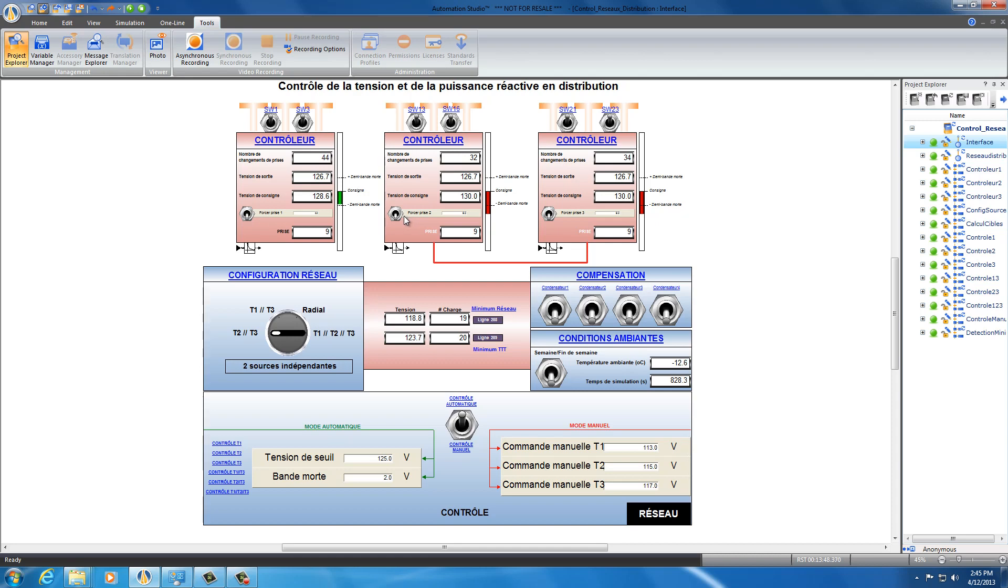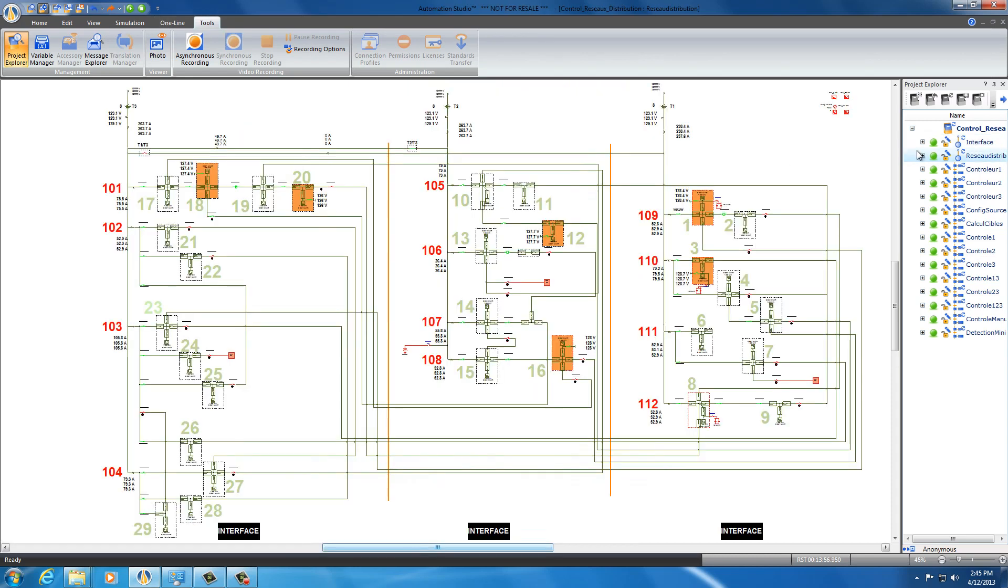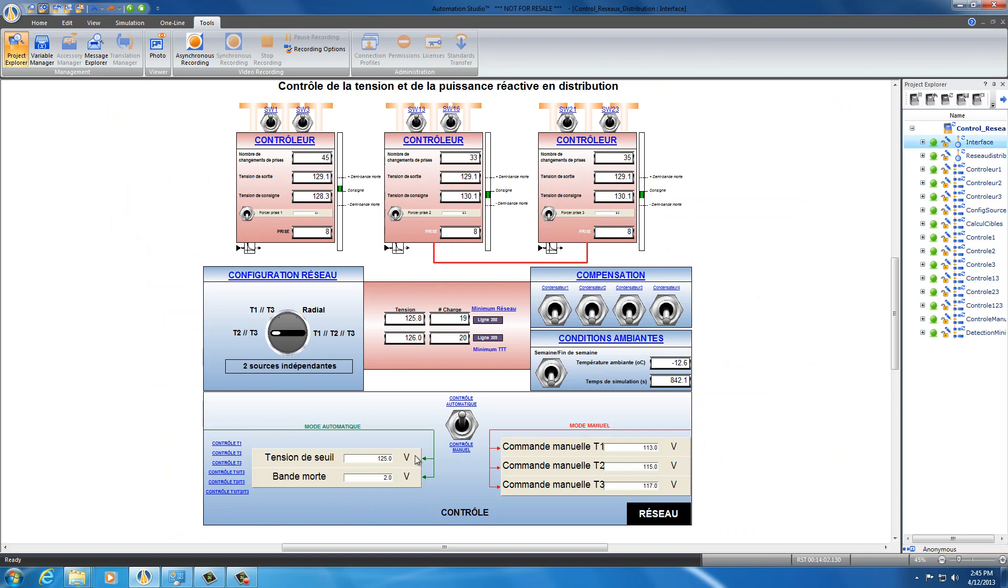Another thing I can explain: the control panel here represents the manual change of the tap of the transformer. Here we have the transformer tap. This is tap number 8. Each transformer in your network located here has 17 taps that can be switched. These automatically get updated depending on the minimum voltage we put here. For example, if we put it again at 115, it's going to choose the right tap in order to have our output voltage.